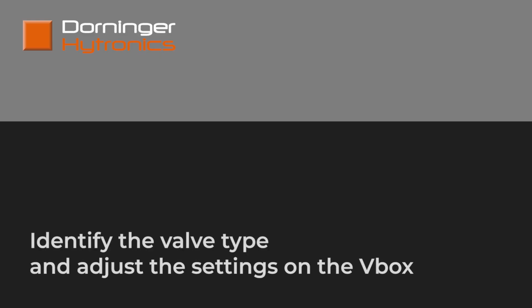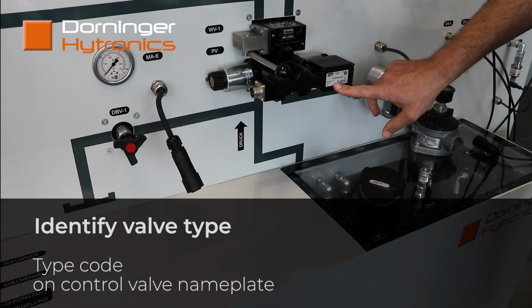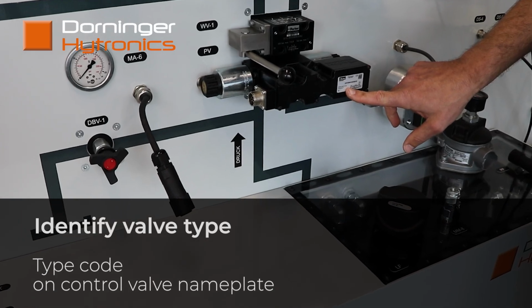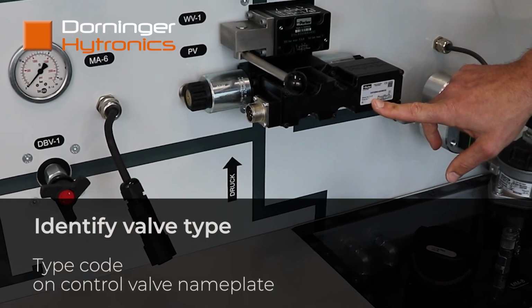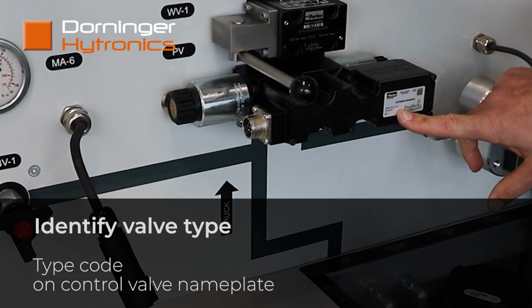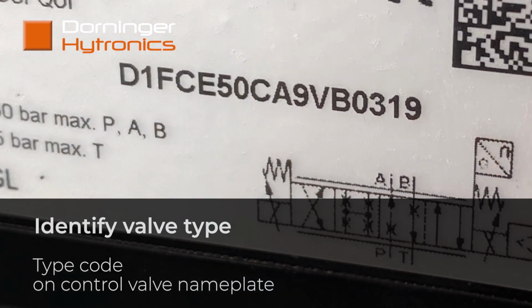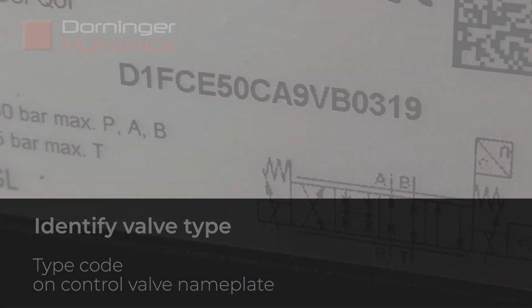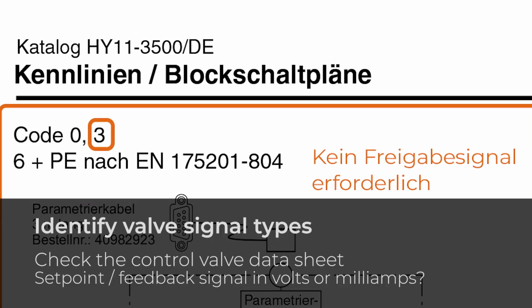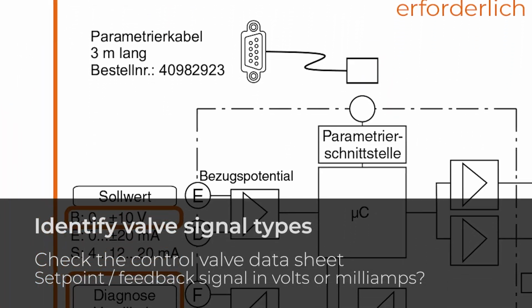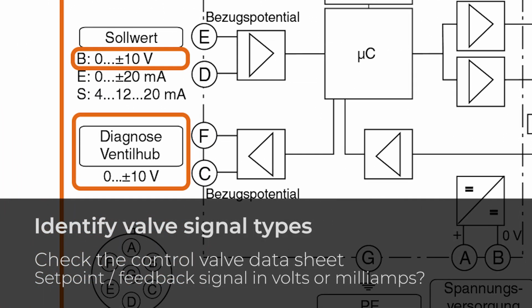First, we identify the valve type. This ensures that the correct interface signals are selected on the Vbox. The type code is read directly from the control valve nameplate. In our example, we use a control valve with the type code shown. We then open the corresponding data sheet and identify the relevant signals. These mainly include the signal type for the setpoint signal and, if available, the feedback or actual value signal.